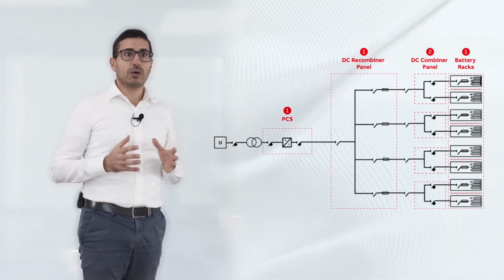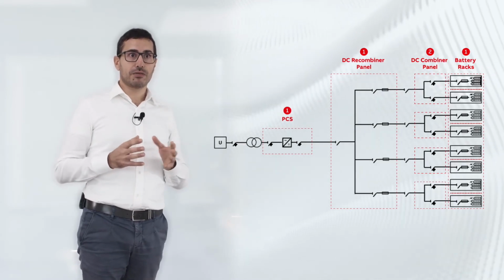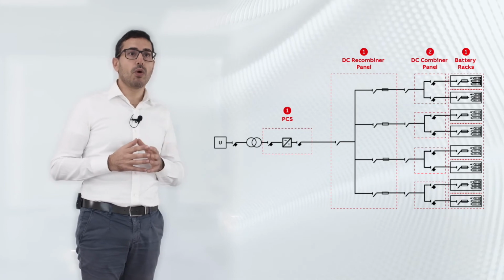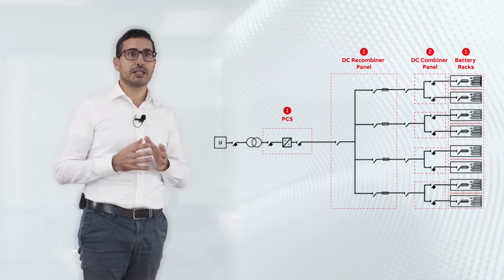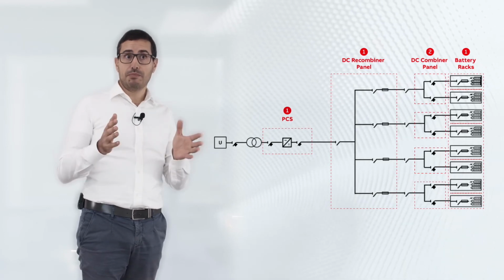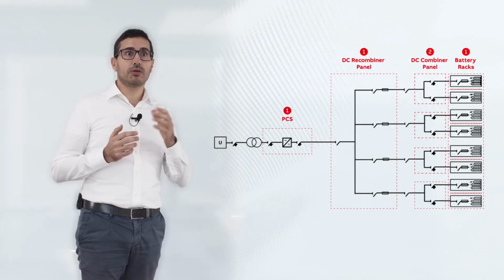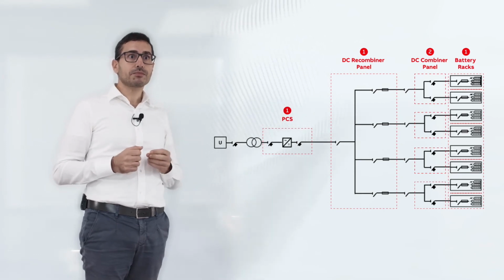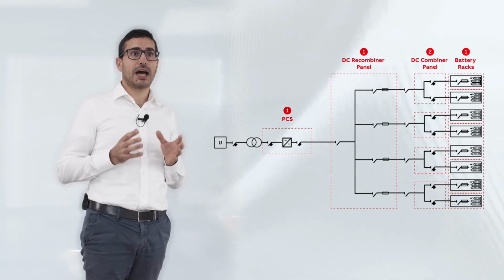The rated voltage of the system is 1500 volts DC. That is a very important rated voltage, well established in solar application and becoming the standard voltage reference also for battery energy storage applications. The system is what we may call a typical utility side of the meter energy storage application, where typical features and functionalities needed are peaking capacity, renewable firming, arbitrage, and black start, islanding.